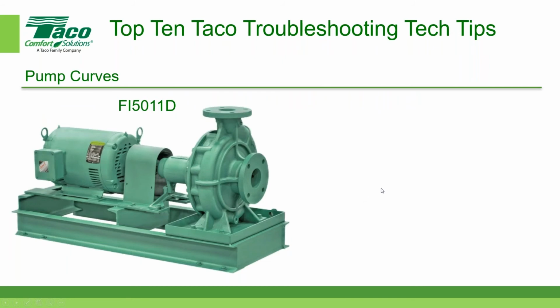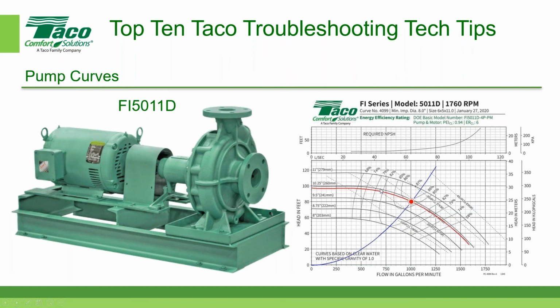That's pretty much what it looks like. And this is the pump curve that goes along with that. And they told us for a single pump operation, it's 1,000 gallons per minute at 80 feet of head. And the red line represents the pump curve and the blue line represents the system curve. Now, today's discussion is not to get into the details of how to read a pump curve, but it's going to help us with the troubleshooting process.